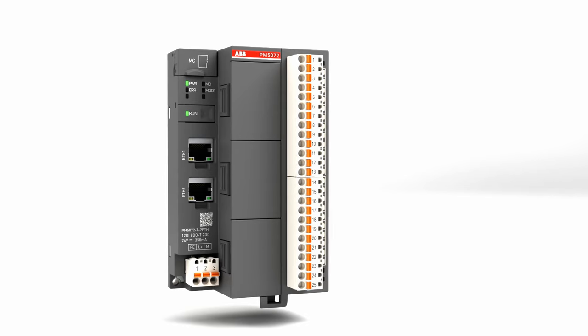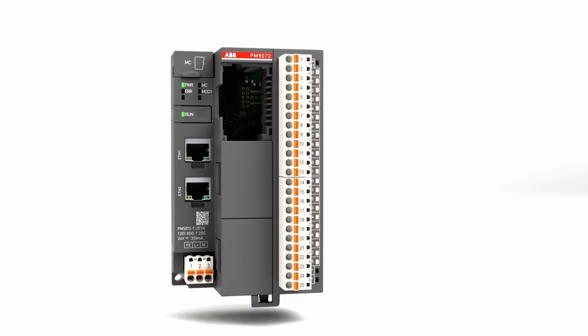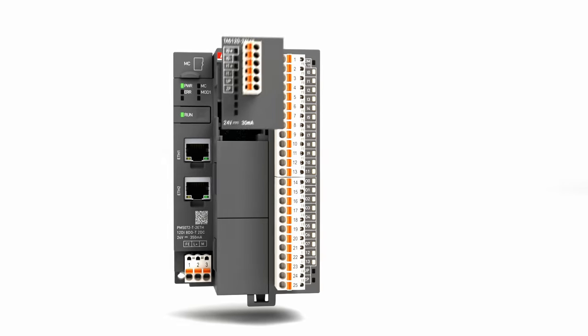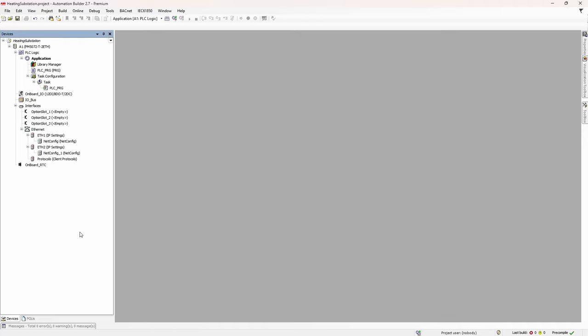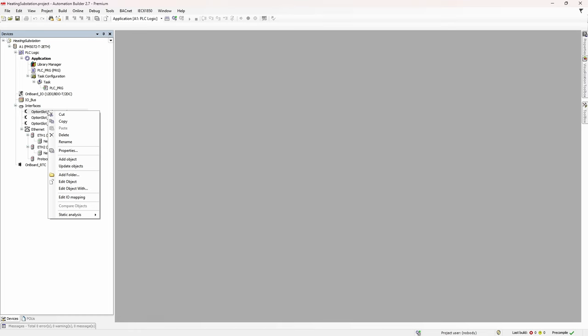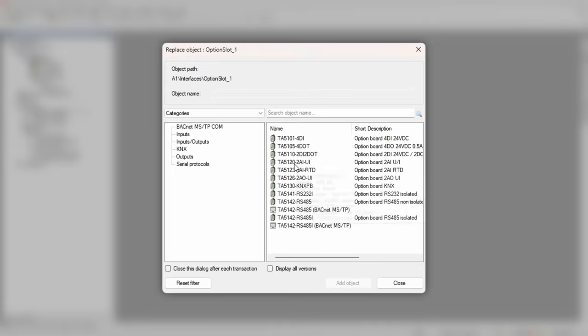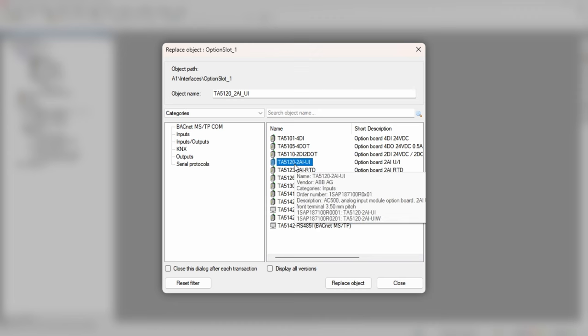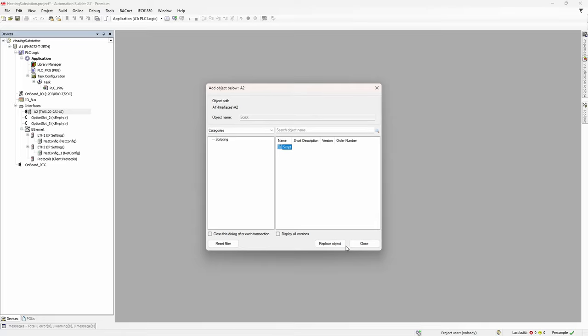In option slot 1 of the CPU, we have analog option board TA5120 inserted. Let's reflect that in our configuration. Right click on the option slot 1 element, select add object, find the option board, give it a name, and click replace object. Option board will be inserted.